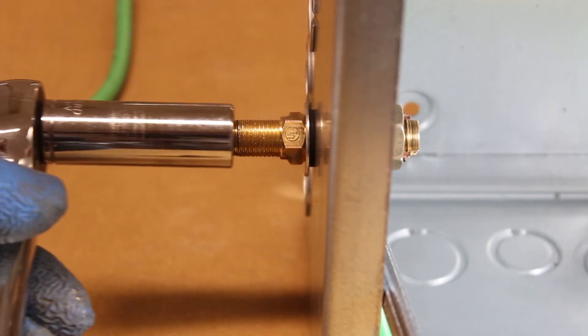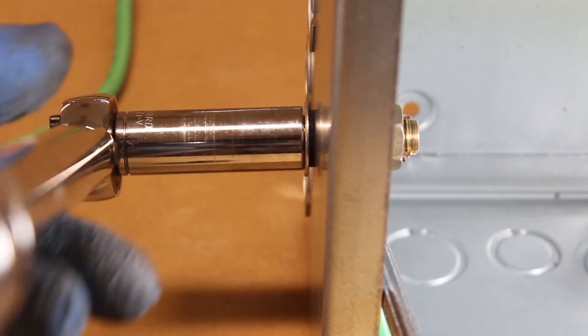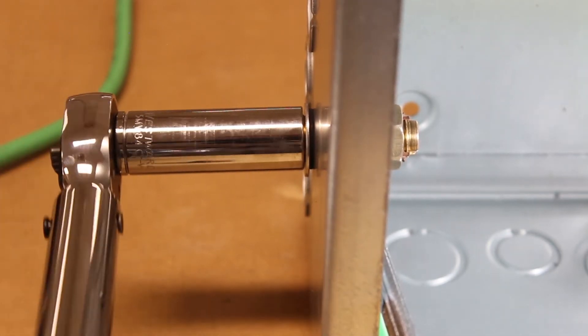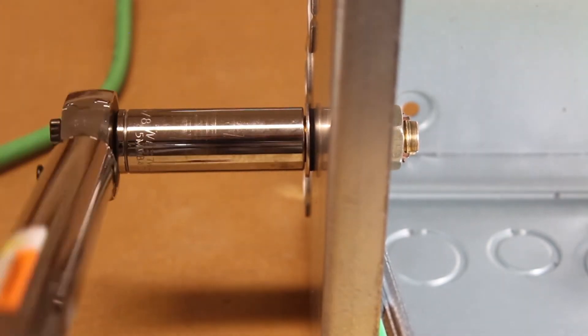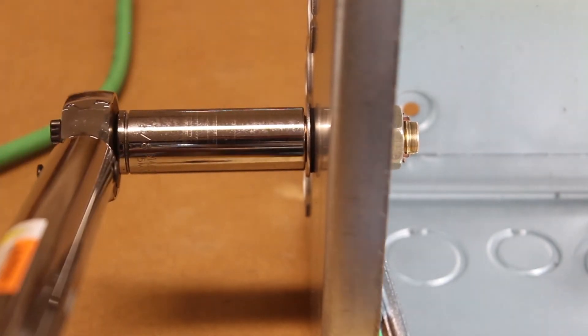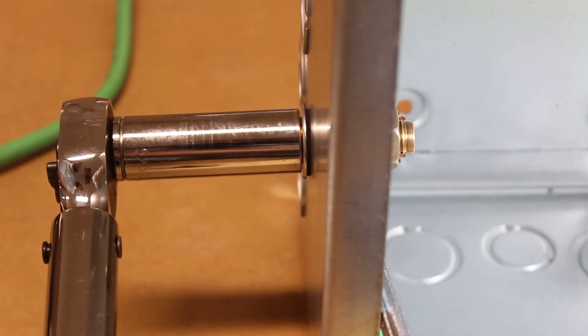A key component to attaining NEMA 4X rating is tightening the components down to the specified torque ratings. With your Burndy torque wrench, torque the connector to the enclosure using the torque specified in the documentation.